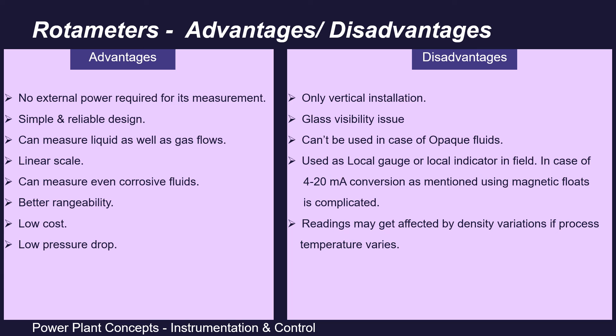Talking about its disadvantages: fluid temperature variation can change fluid density, so calibration done at one temperature condition may not give correct readings at different temperature conditions. Second, it can only be used in a vertical orientation. Third, glass tube visibility can be an issue, and it cannot be used with opaque fluids. Also, as commonly seen in power plants, it is generally used as a local indicator — converting to 4–20 mA using magnetic floats is a bit complicated.